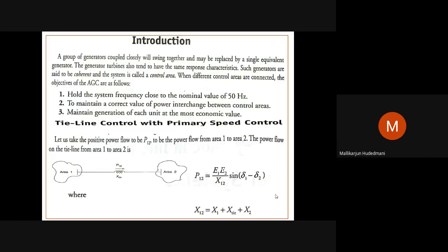Therefore, you should see to it that you schedule the generators most economically, the cost effective units which are optimal in producing megawatts for a requirement, and the usage of fuel is so optimal that they reserve fuel for future use also. These are the three things that should be kept in mind for an AGC in an interconnected operation. Then, why is the last parameter important?